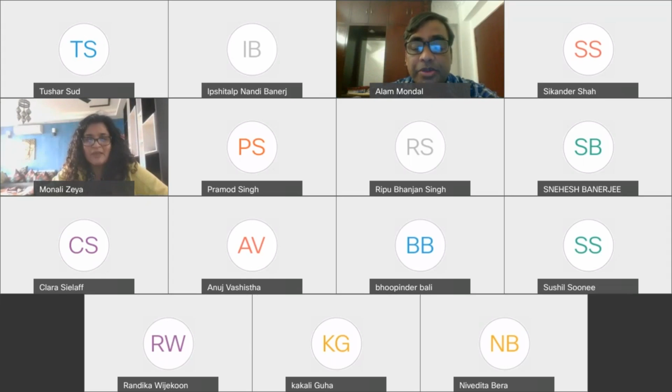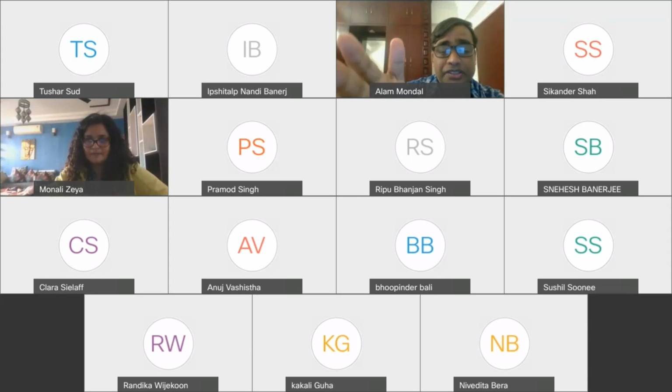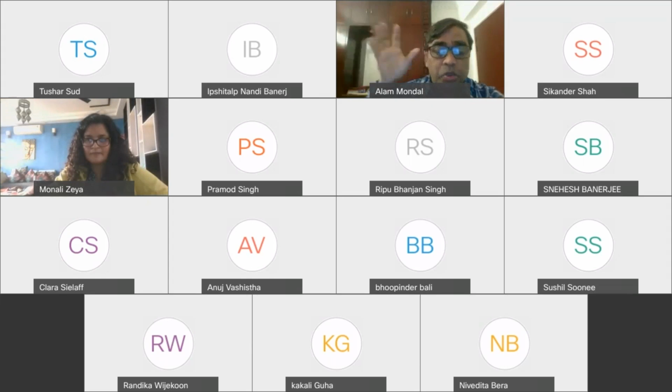Yes. I should also add that the national grid code now available clearly mentions up to 20 megawatts. So the distribution system can be used for power evacuation, but for more than 20 megawatts you have to use the transmission lines. So when we need the transmission system for power evacuation, we have to go further.